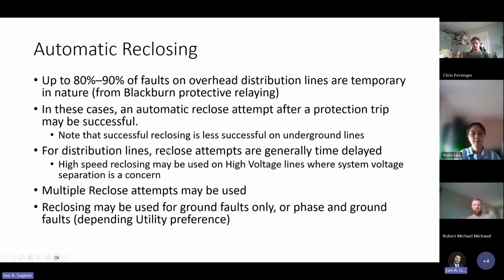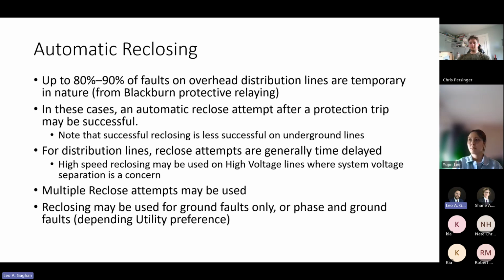For distribution lines, these reclose attempts are generally time delayed, kind of like what we saw in the lab last Tuesday, right? We would do that test trip, and then maybe 10 to 15 seconds later, we would do that reclose attempt. Good to give that squirrel time to really finish burning and fall. And then multiple reclose attempts may be used for various different reasons. Sometimes it is to coordinate with different sectionalizers or upstream or downstream reclosers, or to work with fuse saving schemes. That's pretty common, to use multiple attempts.